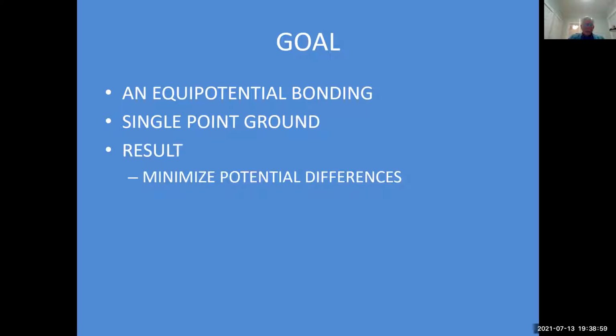Remember, if you have your coax coming in from a tower to your rig, you have the shield, and many people will say, well, I don't want to bond the tower to the rest of the ground system. Don't need to, it's too far away. You still have now a source of potential coming in, and in the same equipment you're going to have your green wire, your equipment grounding conductor from your house supply, and they're going to be at different potentials if there's a lightning strike or an electrical fault. So you really want to minimize that by bonding things together.